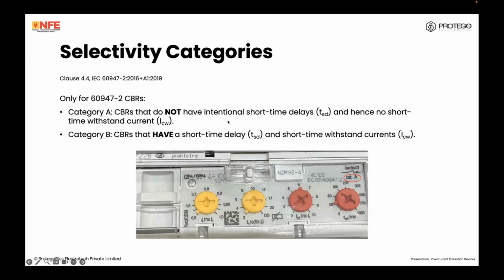Now, selectivity categories are interesting. So you got, let's say, a main distribution board supplying a building. Then per floor, you have individual floor distribution boards, and per load or per circuit, you have your RCBOs. What happens is, if there is a fault in a final circuit, say a socket circuit, you do not want the entire building to lose power. At the same time, you do not want the entire floor to lose power. So these upstream breakers, I will get into selectivity in greater detail later, have to have a time delay.